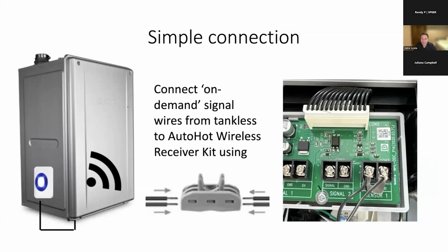In California, we have very strict energy code requirements for new construction and recirculation, where they have to do on demand for everything. Timers are basically not allowed if you want to meet the prescriptive energy code requirement. So as a result, all of the tankless manufacturers have a little two-wire connection to put a little hardwired button or a hardwired switch. So all you have to do is connect the receiver to that little terminal that's located on the circuit board, and that turns it into an on-demand system.